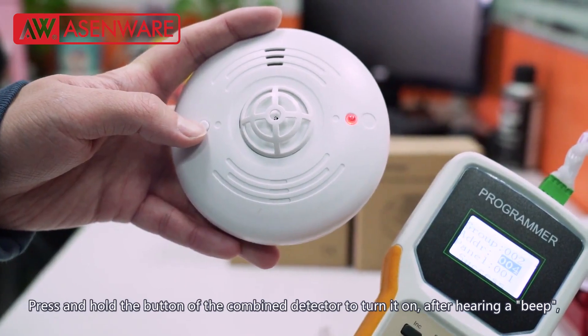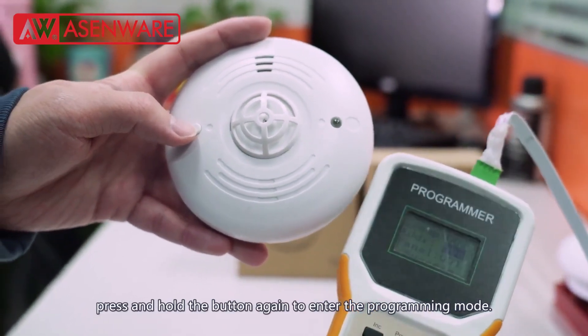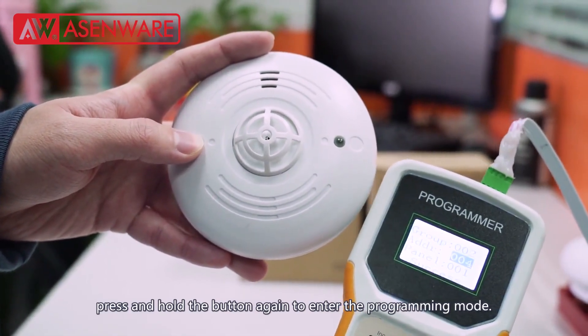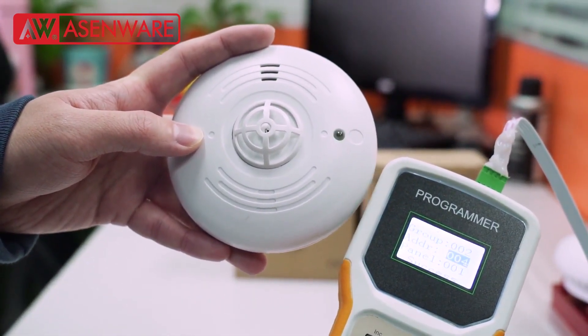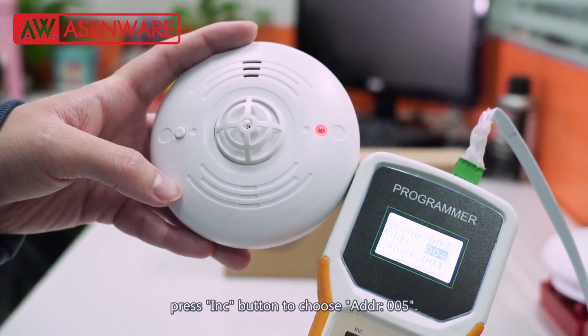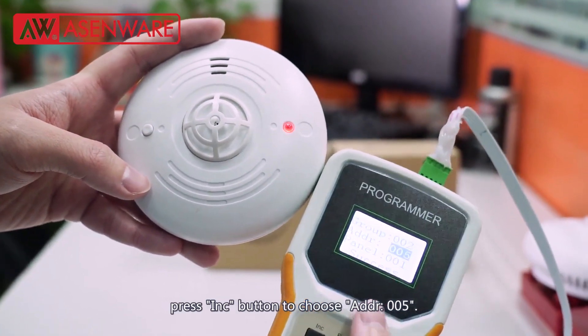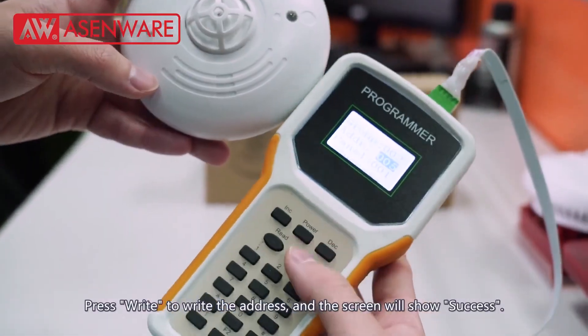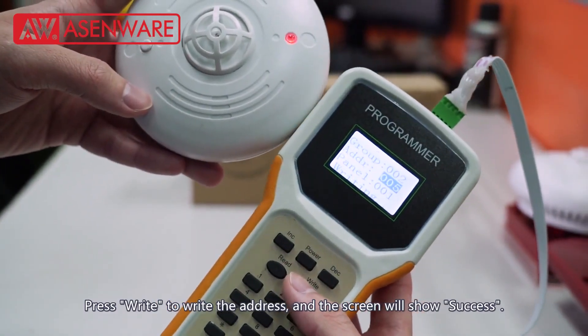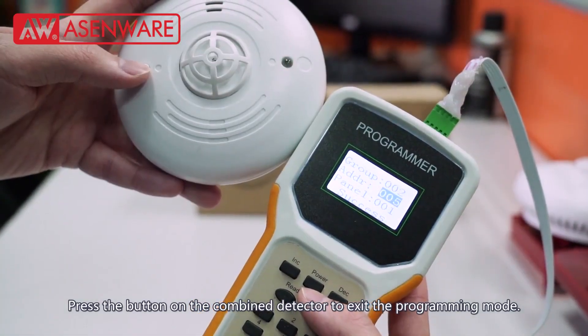Program the address of the wireless combined detector. Press and hold the button of the combined detector to turn it on. After hearing a beep, press and hold the button again to enter the programming mode. Group 002, Panel 001 remains unchanged. Press the increase button to choose address 005. Press "Write" to write the address and the screen will show success. Press the button on the combined detector to exit the programming mode.